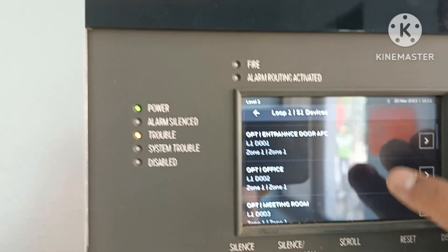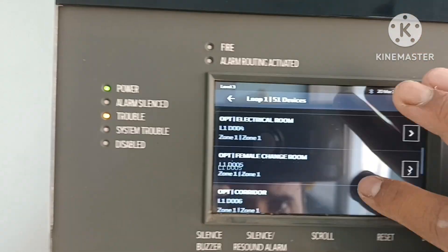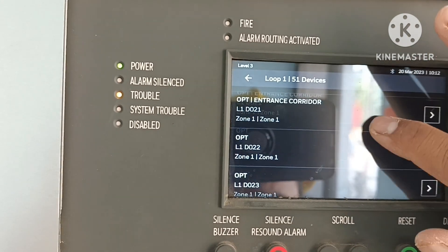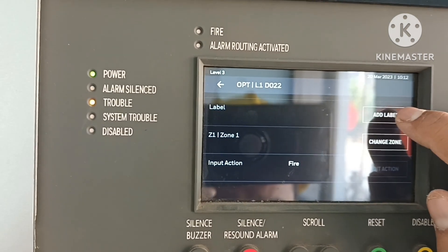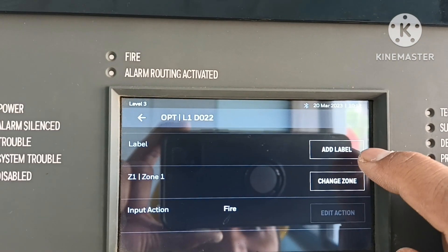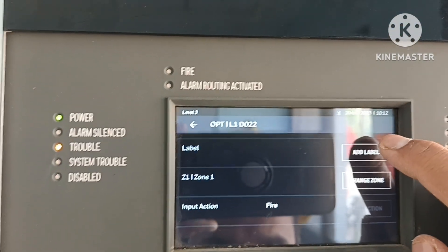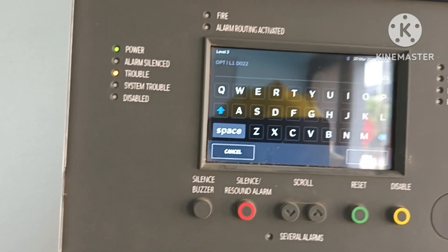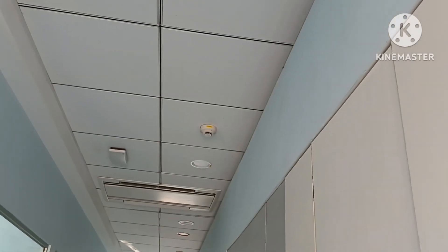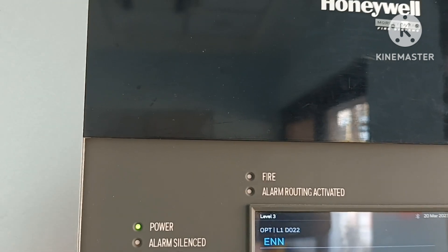I have already set up device 1. Now I will go to device 22. This is an input device — we go here to add a label. When you select the device, the add label option appears. We have to check the drawing to find where device 22 is located. In the drawing, it is located here — device 22 is in the entrance corridor. We will put here 'ENT' for entrance.